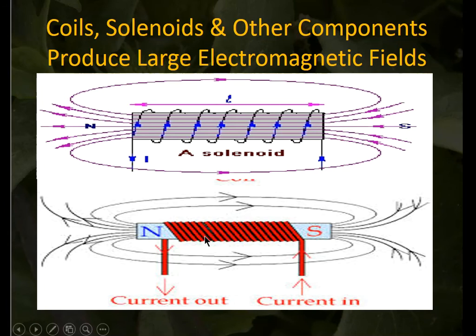Now, the other thing that we're concerned about is our environmental electromagnetic field issues that exist in every location, because every location that has electrical wiring has electrical fields. These are electromagnetic fields caused by the passage of current through wires. And the passage of current through wires produces electromagnetic fields. Depending on the intensity of that current in that circuit, it can produce an electrical field that can extend out into the room by several feet. So it's something to pay attention to.